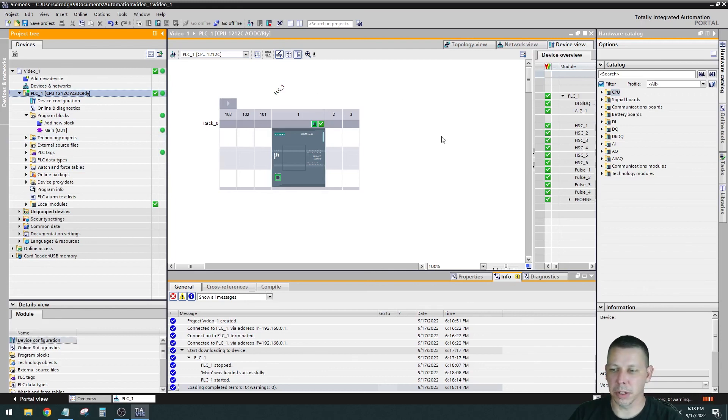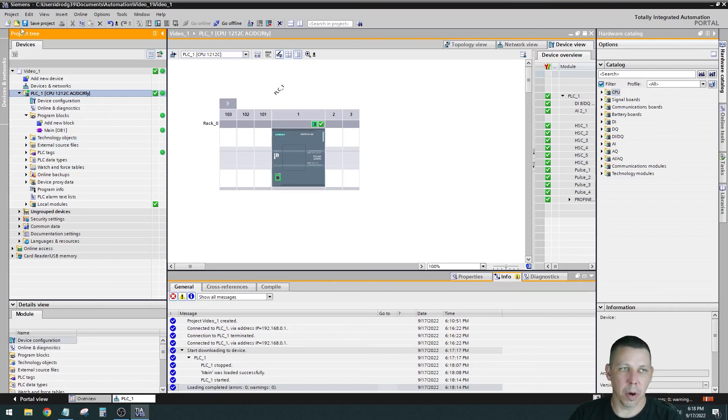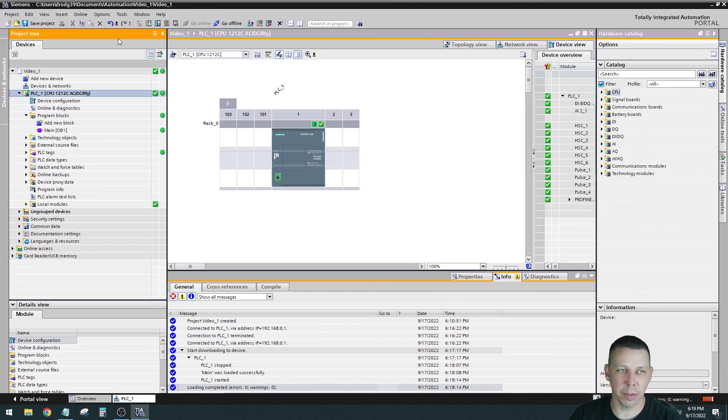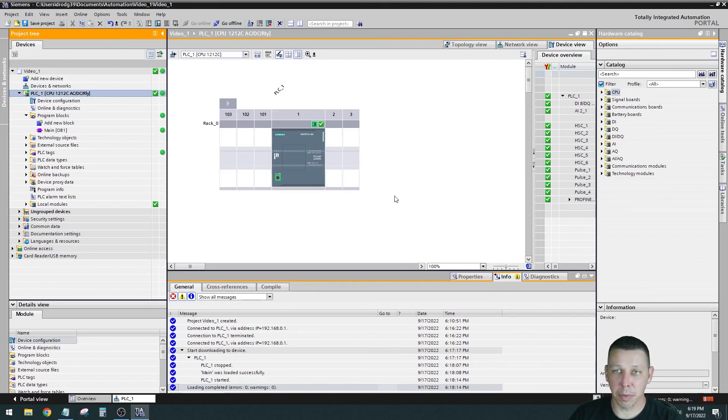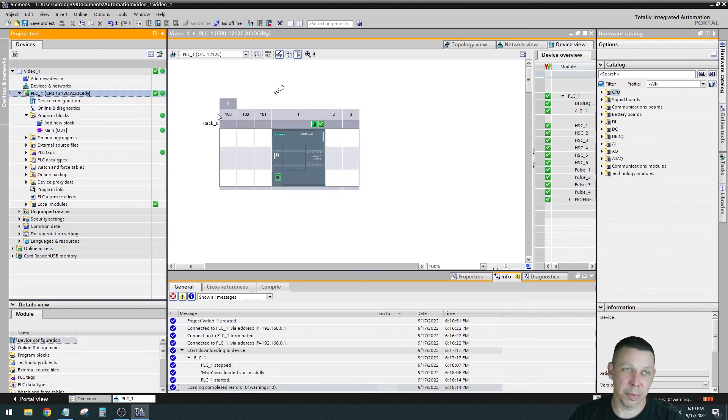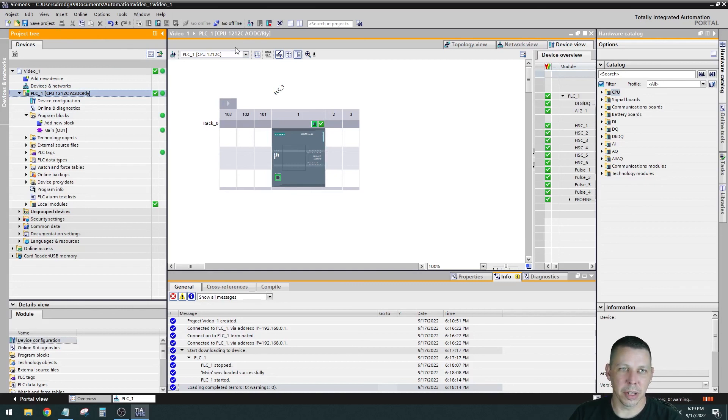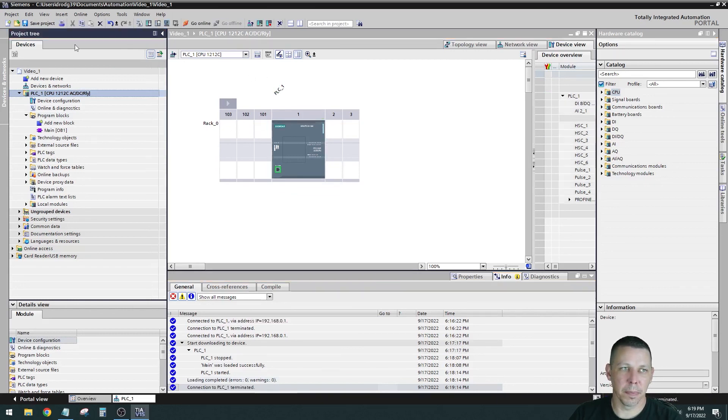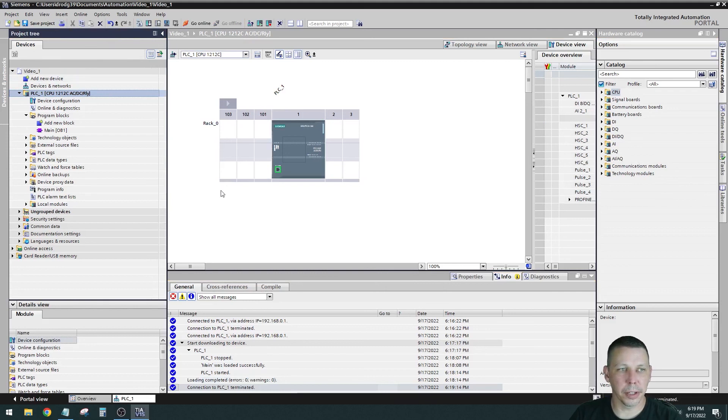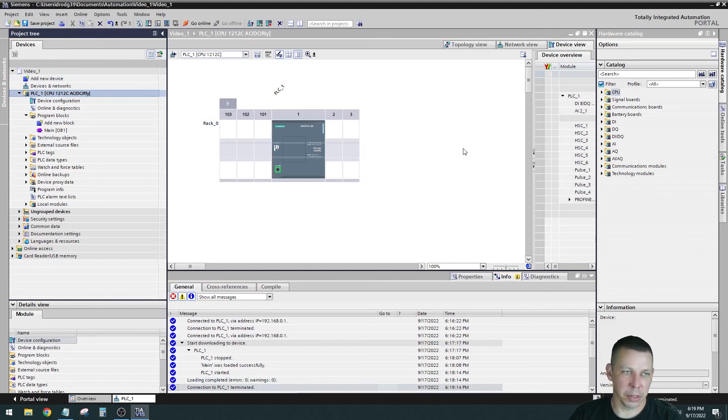I'm going to make a series of shorter videos instead of one long one. Orange means I'm connected to it - I'm sending and receiving packets back over the ethernet. The processor may or may not be in run mode, it'll still be orange. I might not have any logic in the processor, it'll still show orange. Orange just means that you're online. So if I go offline up here, you see the orange goes away and it goes back to like a purplish blue color. Now you are not online with the processor anymore.